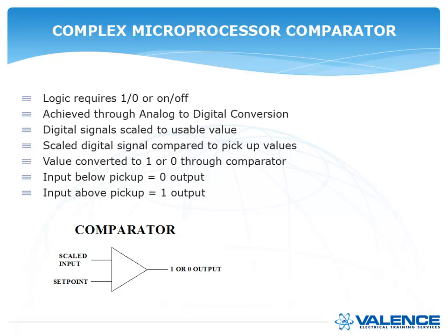The set point is a number that somebody types into the relay, but the scaled input goes through an analog to digital converter. So if you have 5 amps going into the relay, there's an analog to digital converter that converts that 5 amp analog signal into a 5 amp digital signal. Then if 5 amps happens to be greater than the set point, the output of this comparator will be a 1. If 5 amps is lower than the set point, the output will be a 0.